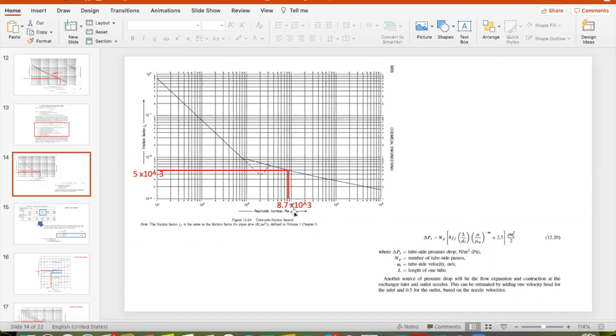Let's get the friction factor to calculate delta P with equation 12.20 for the tube side. Our Reynolds number is 8.7×10³ with the values given for velocity and diameter. We are more or less in this area on the graph — there is only one line so you don't need to choose another. We go all the way to the left and we get a friction factor for the tube side of 5.1×10⁻³.